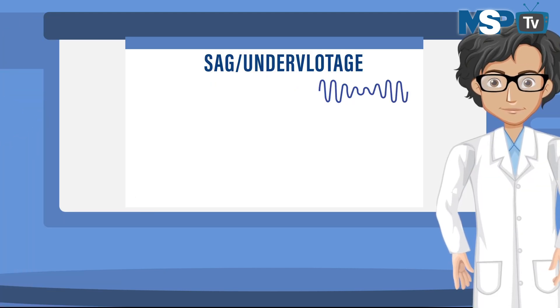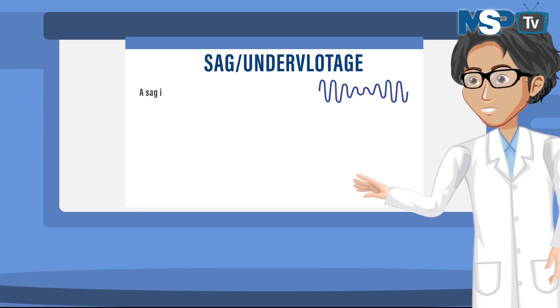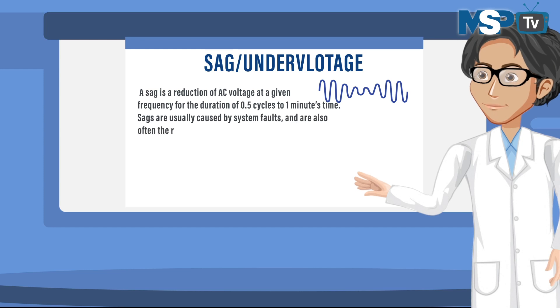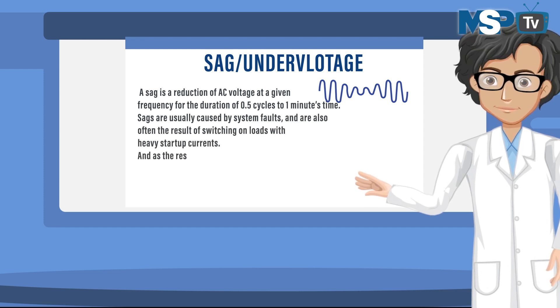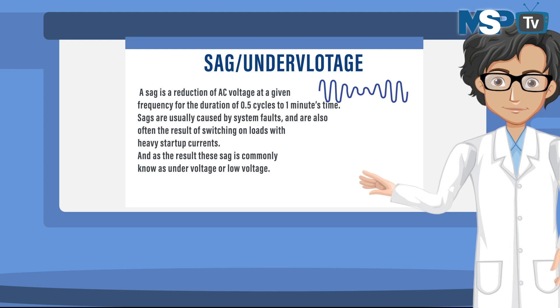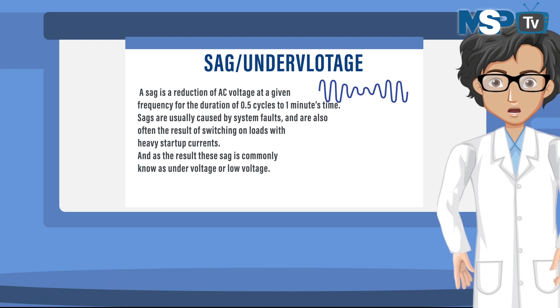The third problem is sag or under voltage. A sag is the reduction of AC voltage at a given frequency for a duration of 0.5 cycles to one minute. Sags are usually caused by system faults and are also often the result of switching on loads with heavy startup currents. As a result, sag is commonly known as under voltage or low voltage.